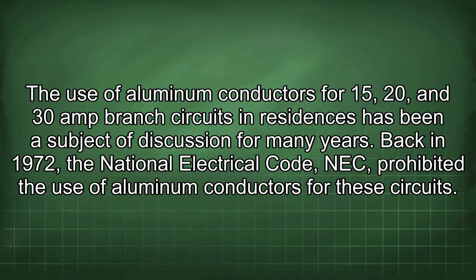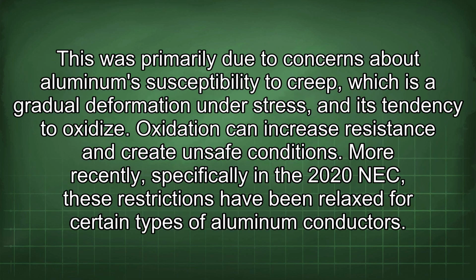The use of aluminum conductors for 15, 20, and 30 amp branch circuits in residences has been a subject of discussion for many years. Back in 1972, the National Electrical Code, NEC, prohibited the use of aluminum conductors for these circuits. This was primarily due to concerns about aluminum's susceptibility to creep, which is the gradual deformation under stress, and its tendency to oxidize. Oxidation can increase resistance and create unsafe conditions.